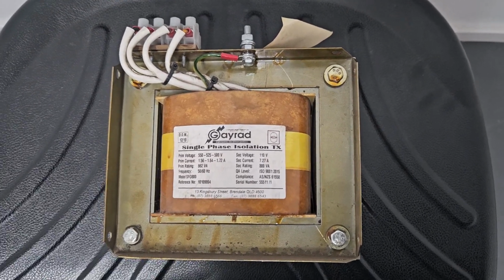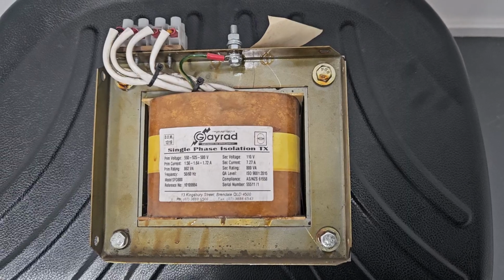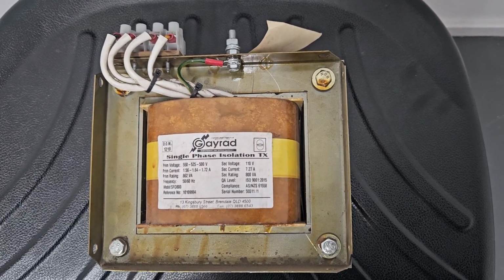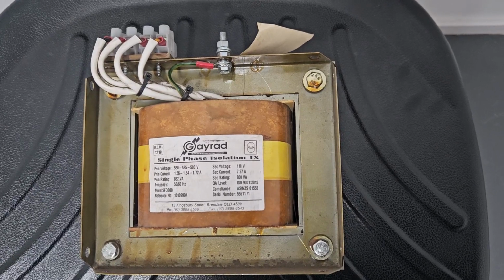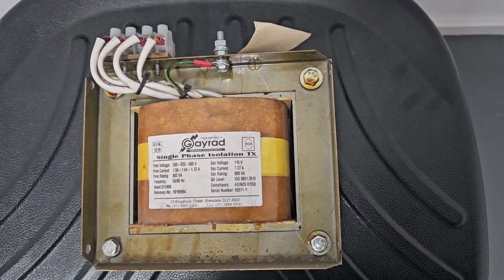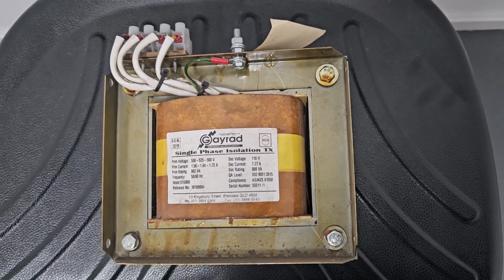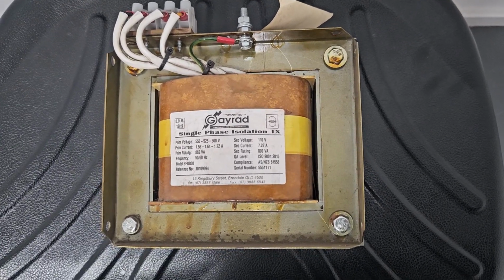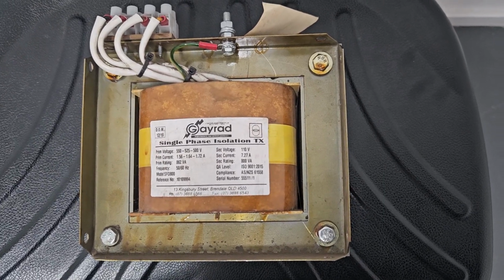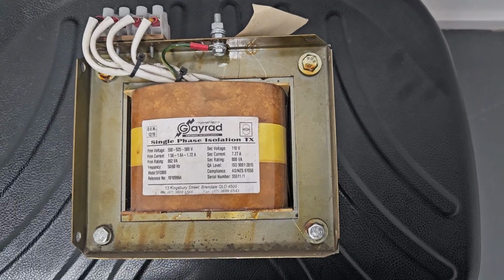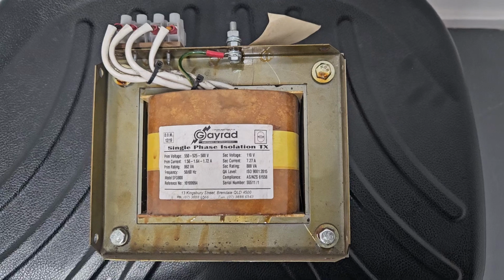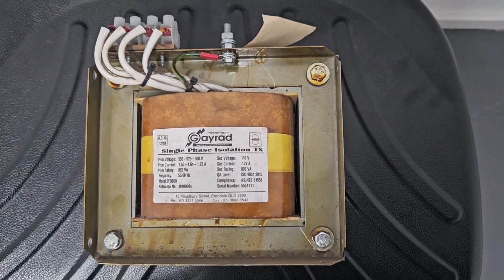But you also get isolation transformers. Isolation transformers have a 1-to-1 ratio. When you want to separate two electrical circuits, you're going to have a primary winding and a secondary winding, then the voltage on the primary, let's say it's 500 volts, and the voltage on the secondary is 500 volts, but the two circuits are electrically isolated, hence the name isolation transformer. So it isolates two circuits. All right, now you understand the function of a transformer. Let's go to the components.